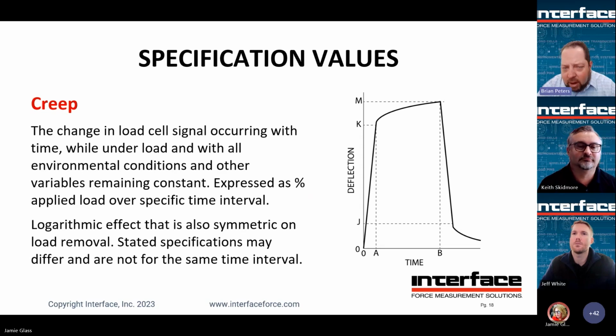Creep. So creep is a physical phenomenon that all mechanical and physical elements respond to. And essentially, it's a very slight change in deflection over time, even when you're applying the same load. So as far as a sensor is concerned, the creep spec would quantify how much the signal might deviate as you maintain that constant load. Now, the goal is that in the case of our load cells, which are foil-based strain gauge Wheatstone bridge elements, the gauges respond identically from a creep standpoint to whatever material they're bonded to, right? The key takeaway here is a couple. One is that it's a logarithmic effect. So most of the influence happens relatively early and then it decays over time.